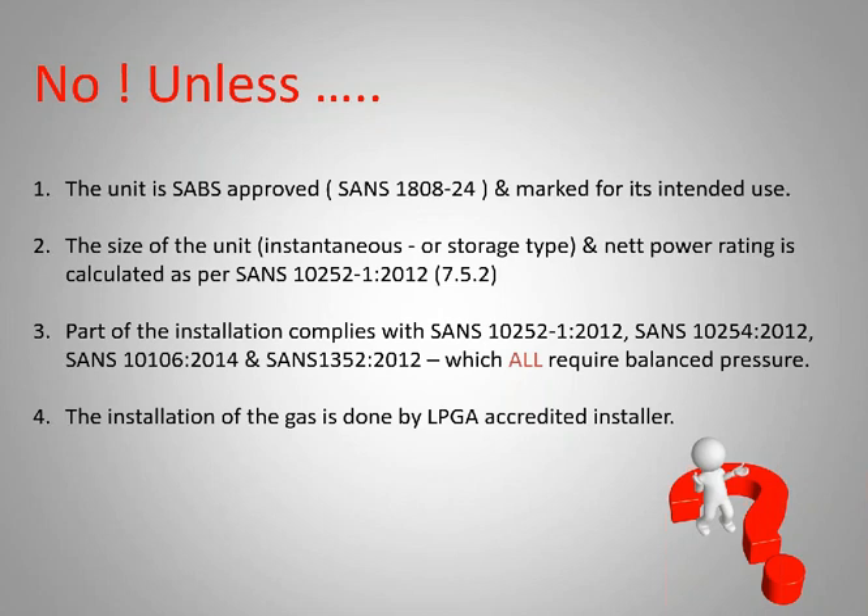All of those documents require your hot and cold water to be balanced — within 20 percent. You should be able to install these lines without more than a 20 percent drop on the water supply. I'll show you the calculations now.